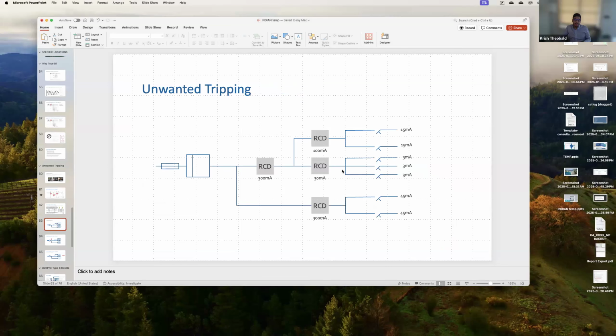See, unwanted tripping: if you sectionalize, see here, a 100 milliampere RCD with downstream devices, so 100 times 0.3 is 30. So 15 and 15, 30. This is fine. 30 milliampere times 0.3 is 9 milliampere. For this, 300 times 0.3 is whatever value that is. Yeah, this I understood, sir.